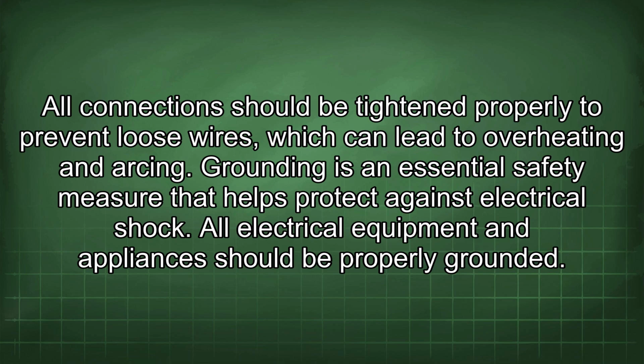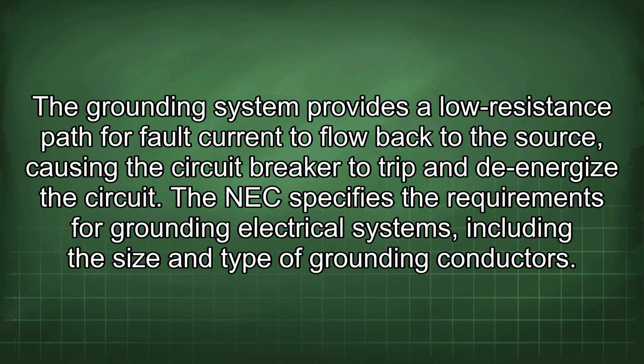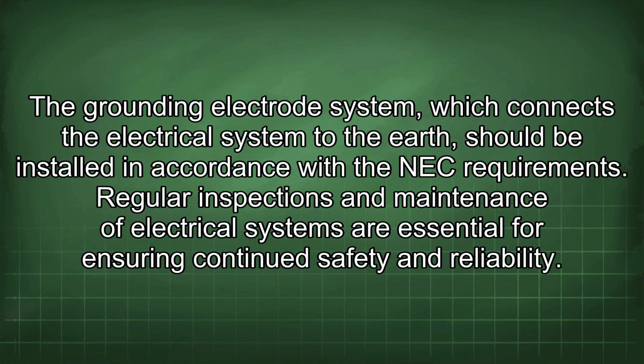Grounding is an essential safety measure that helps protect against electrical shock. All electrical equipment and appliances should be properly grounded. The grounding system provides a low resistance path for fault current to flow back to the source, causing the circuit breaker to trip and de-energize the circuit. The NEC specifies the requirements for grounding electrical systems, including the size and type of grounding conductors. The grounding electrode system, which connects the electrical system to the earth, should be installed in accordance with the NEC requirements.